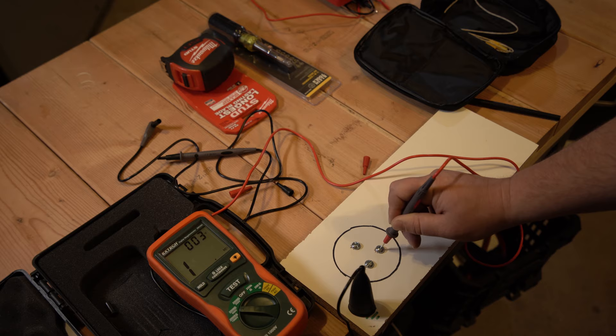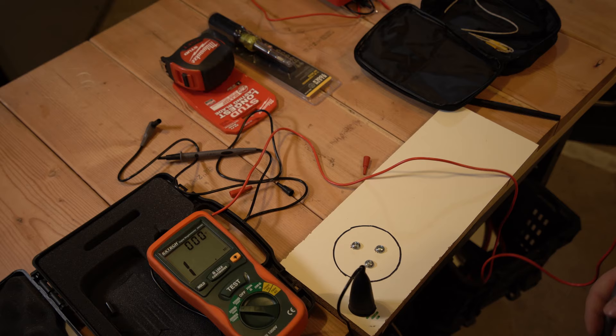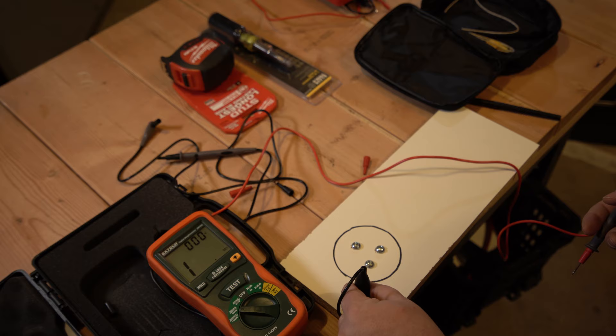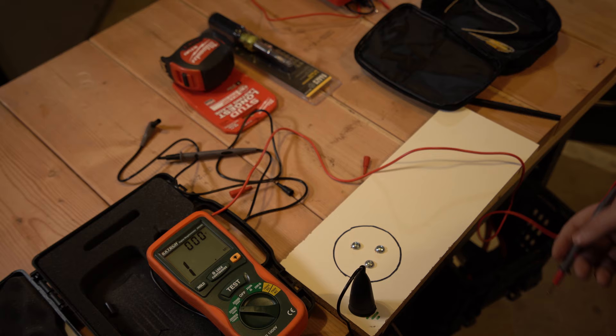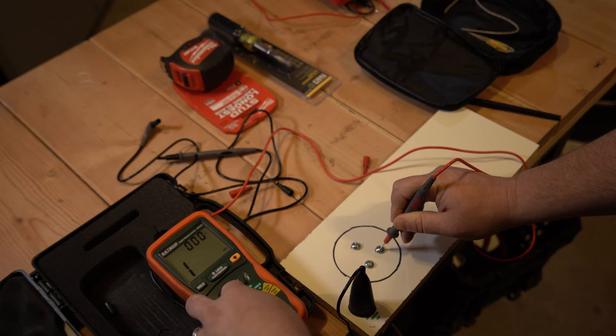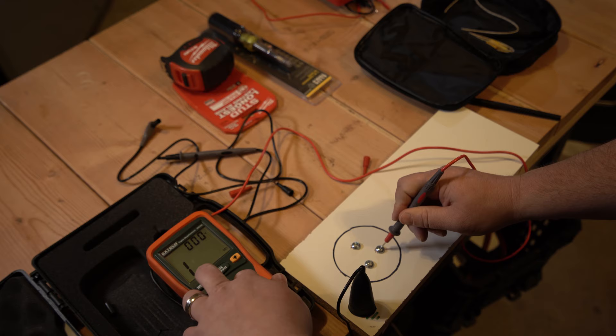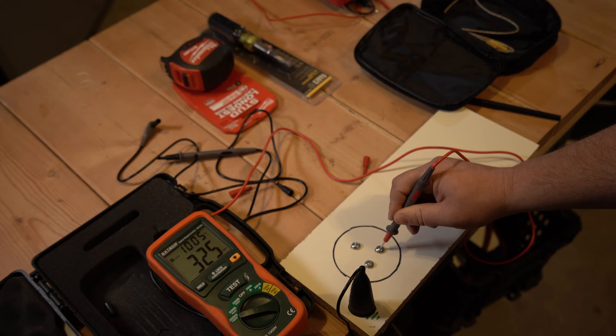You can do that through all three leads, or on like a three-phase motor, typically if they've got the wires hanging out of them I'll just clamp this onto all of those leads at once, check to ground, run the test and see if I've got any, or record whatever resistance it is to ground and go from there. For that one you saw that we got nothing to ground, so now let's go ahead and check a little bit higher resistance value up to 2000 megaohms. We'll hit test here and lock it.